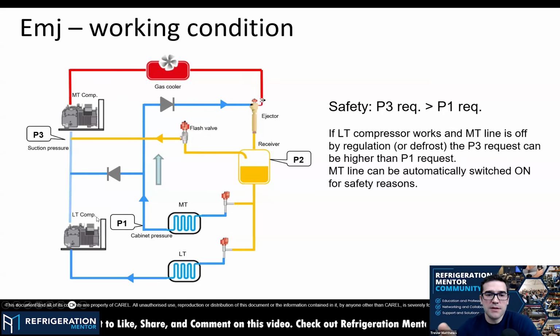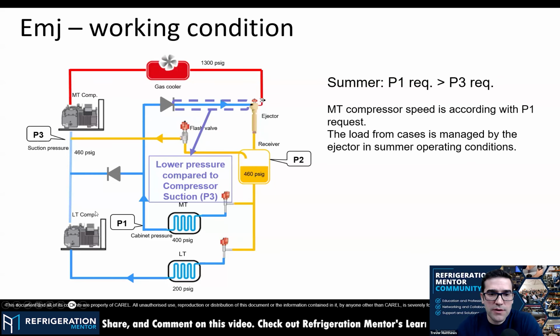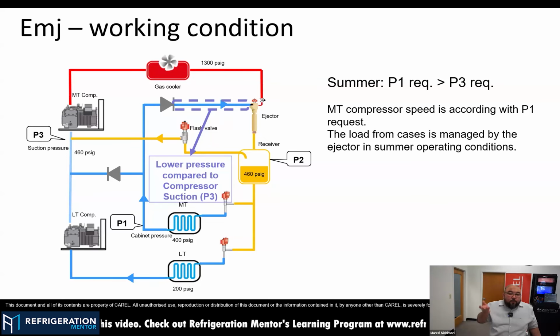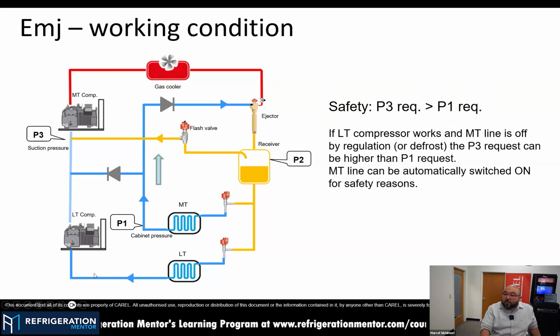Yeah, it makes sense because you're running your medium temp, say 400 PSI, and that's 460 coming from the ejector. So it totally makes sense. So we can increase the pressure on the MT suction line, and we start getting more benefit from the ejector.